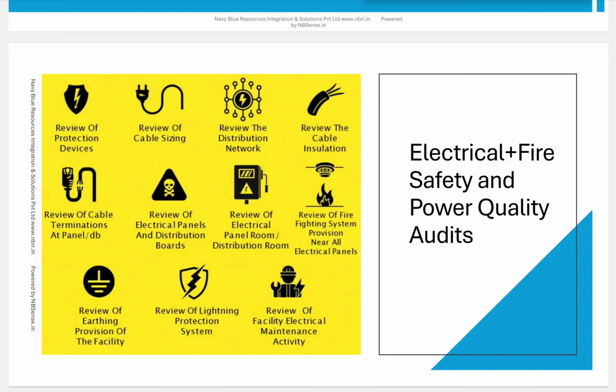The next part within electrical audit is the power quality audit. We measure and check power quality issues in the electrical distribution system — especially power factor, harmonics, transients, flickering and other abnormalities — using a power quality analyzer, and through data analysis we provide findings and recommendations.